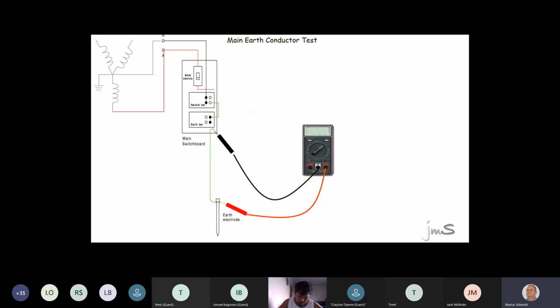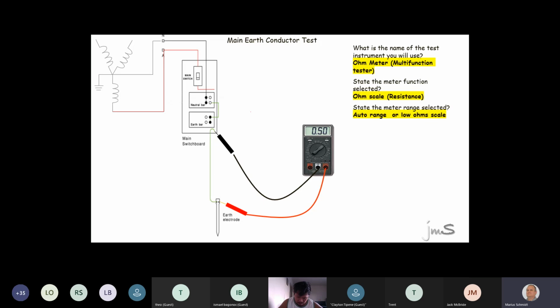But before we do the test, you're going to take your multimeter leads and see if you get 0 ohms. Prove. Do a test. Do a prove again. Now, guys, when you measure there, boom, is that okay? See the reading on my meter? Just. Right. So what instrument are we going to use? Ohm meter. If you have to select a scale, you always choose the lowest ohm scale. Right? Lowest ohm scale. To carry on, when you do the test, a lot of your multimeters have an auto range scale. The meter will decide. Now guys, I'm telling you now, in the exam, they love to ask questions like, what instrument, where do you measure between, and what is the reading, or what scale do you put it on?